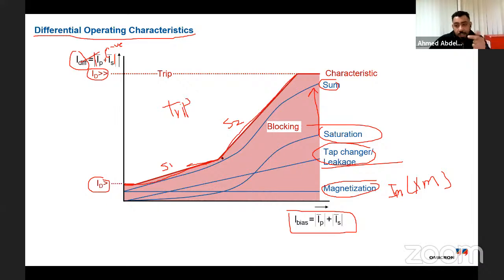Then I will slightly try to change this nonlinear characteristic to a linear characteristic to have a dual slope characteristic, slope number 1, slope number 2, or we can call it the differential operating characteristic. Slope number 1 is mainly to cover the magnetization, to cover the tap changer, and to cover the CT ratio error. Slope number 2 is mainly to cover the saturation of one of the CTs. Here, this is the philosophy of the characteristic.